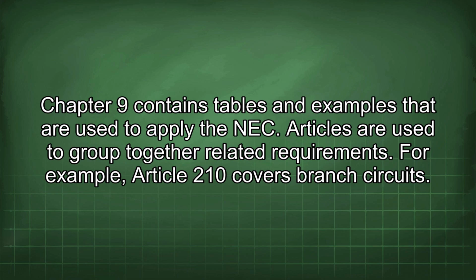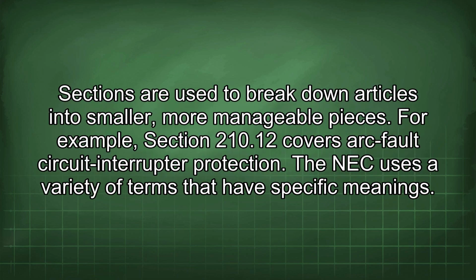Articles are used to group together related requirements. For example, Article 210 covers branch circuits. Sections are used to break down articles into smaller, more manageable pieces. For example, Section 210.12 covers arc fault circuit interrupter protection.